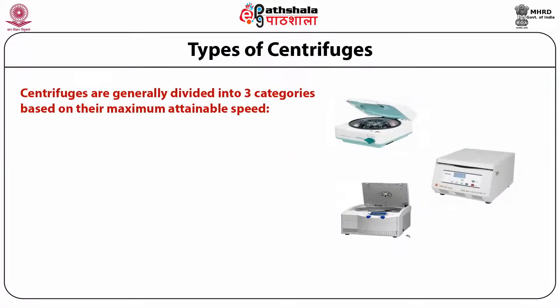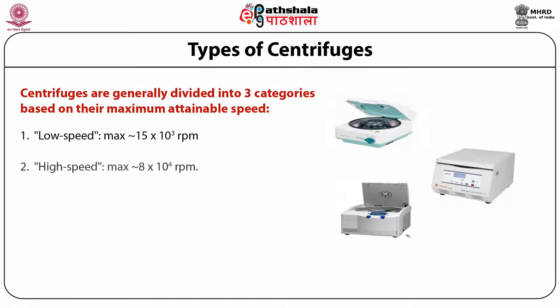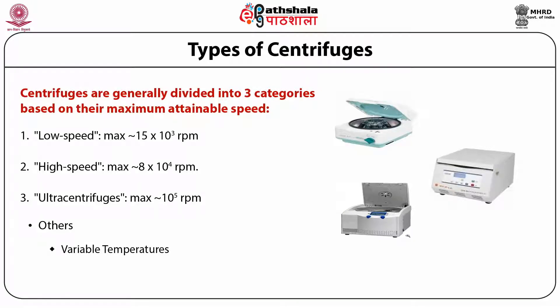Now we will discuss types of centrifuge based on speed, classified into three groups. Low speed centrifugation has a maximum speed limit of 15,000 RPM. High speed centrifuge has a maximum limit of 80,000 RPM. The ultra centrifuge operates at very high speed, more than 1 lakh RPM. Apart from speed, centrifuges come with advanced features like variable temperature control and vacuum capability to control pressure.